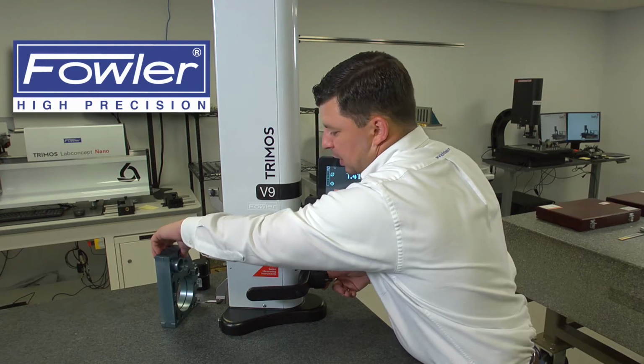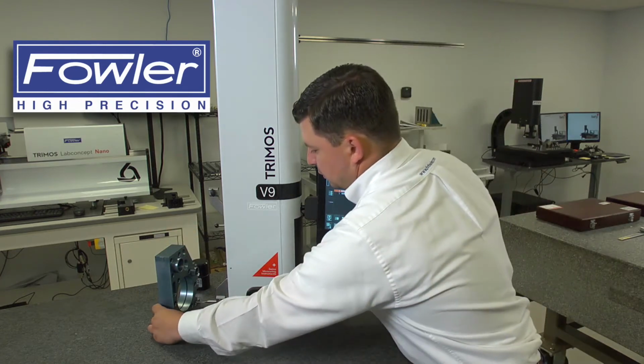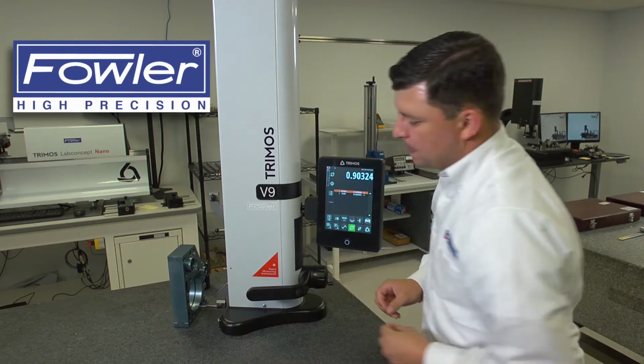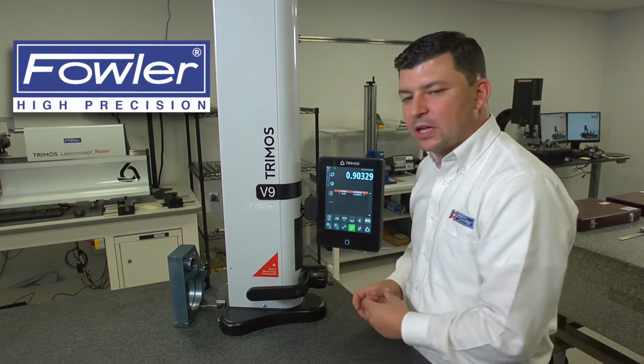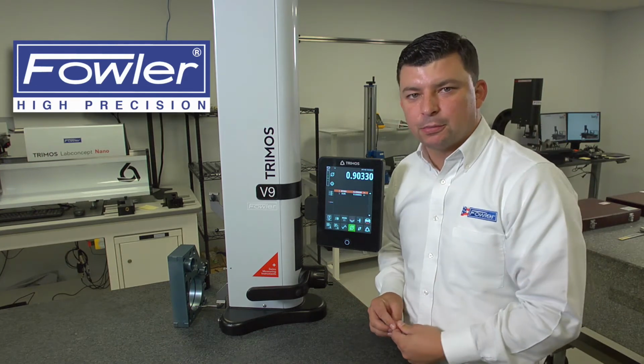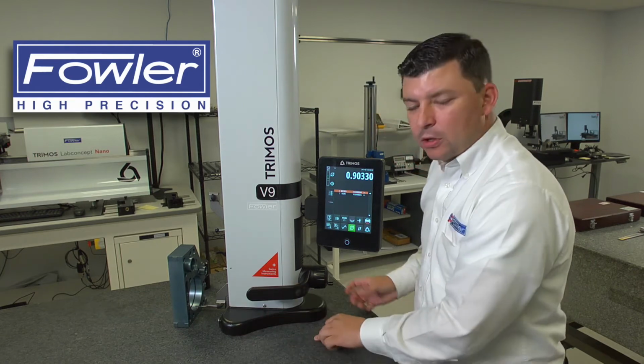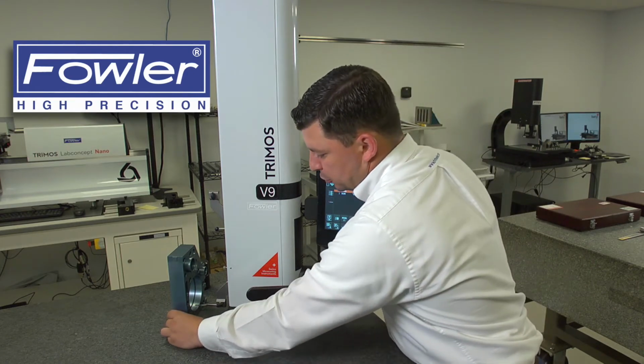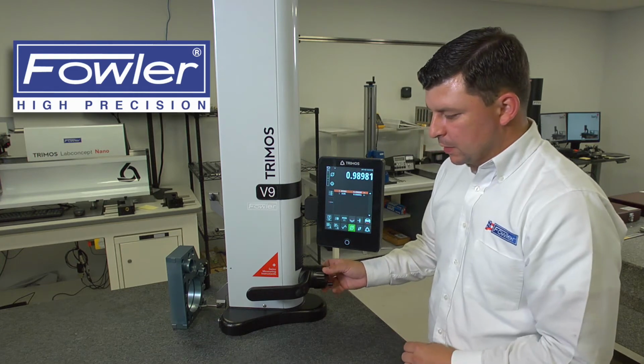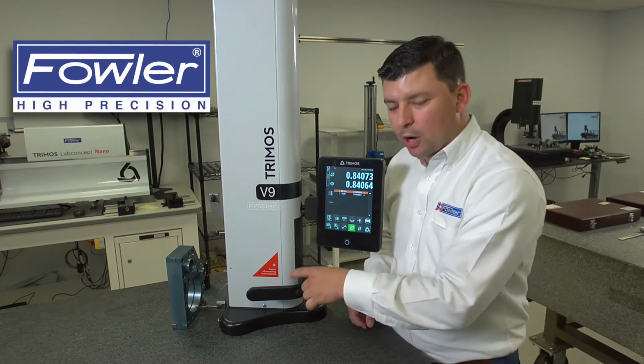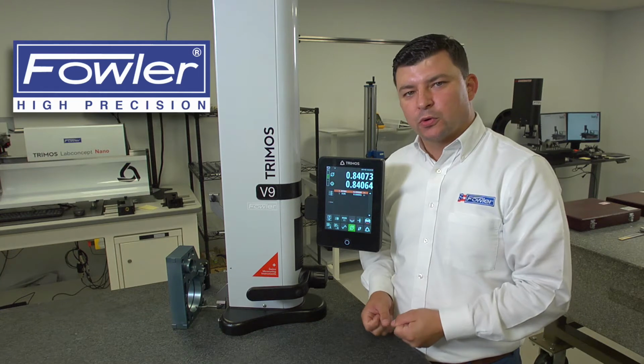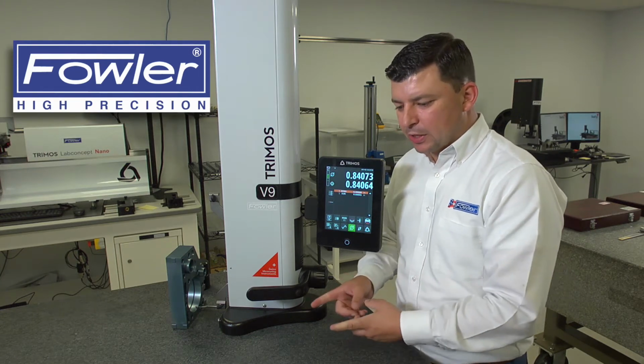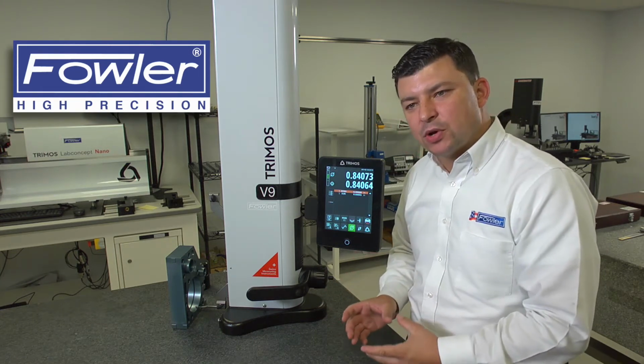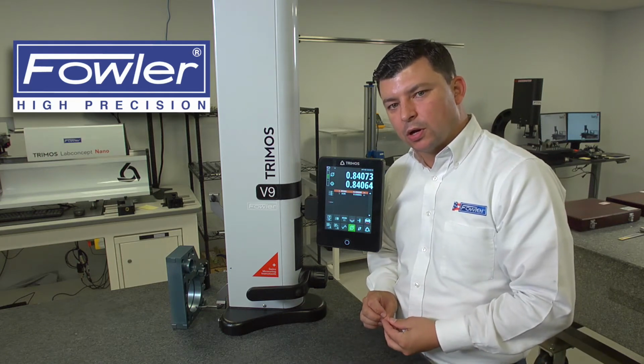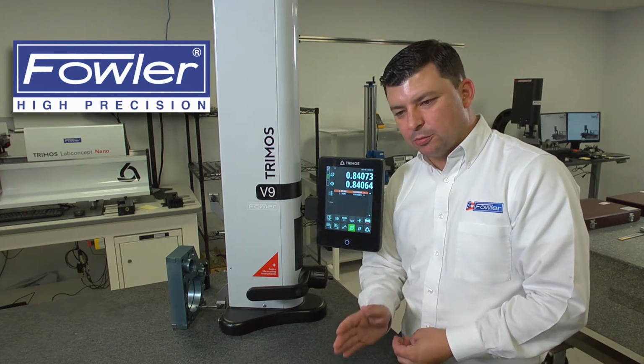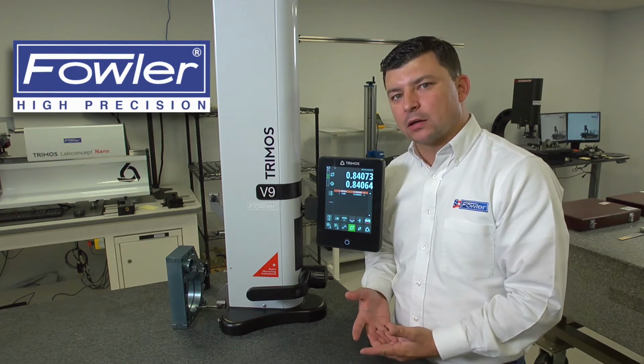At this point, I can measure a diameter. In order to measure a diameter, I need to engage the probe slightly off-center from the reversal point of the bore. So if I've entered relatively close to the reversal point, I will ensure that I'm off-center from that position. I will engage my probe. While my probe is engaged, there's a constant measuring force being applied to this probe. This is going to allow me to have a hands-free operation while I tram through the surface of the bore. The probe will follow the contours of the bore, finding the reversal point for us automatically.